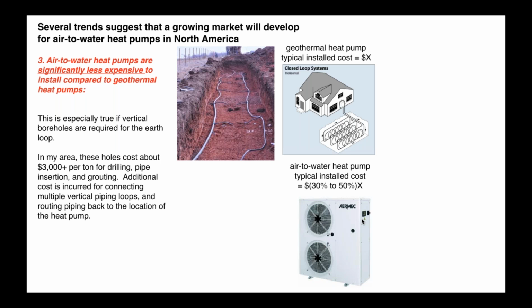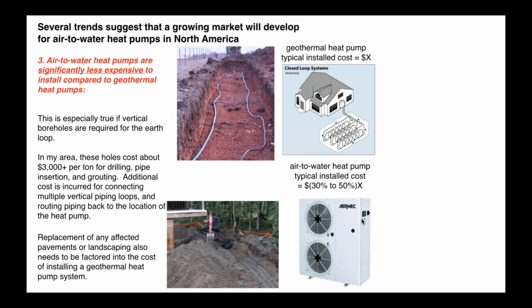And obviously, the cost of geo varies a lot with how the loop's going to be installed. Is it going to be boreholes? Is it going to be a trench? Do you have the land area to do trenches? In my area, vertical systems run about $3,000 per ton just to put the borehole and the pipe in. So that's easily $12,000, $15,000 just to put the earth loop in. And that's obviously a cost you don't have with the air-to-water.